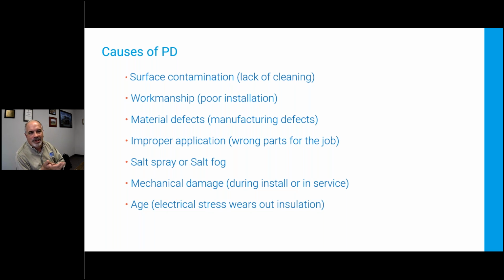Workmanship, poor installation. This is really talking about cable terminations. 70% of the PD failures and the cable failures in the world are due to poor installation. And that varies in what region you're in, but it's a real problem. Manufacturing defects, material defects, you don't get that very often, but you do, occasionally things are built wrong. I've seen extruded cable built wrong. I've seen a variety of things where things separate, you get gaps in it, but manufacturing quality is pretty good. Improper application. You're using the wrong parts for the job. So I'm taking something that's supposed to be spaced this far apart, and I'm putting it into a cabinet that's this far apart, those sort of things.